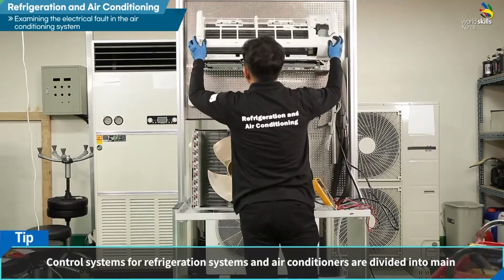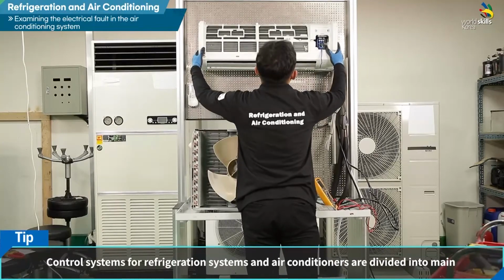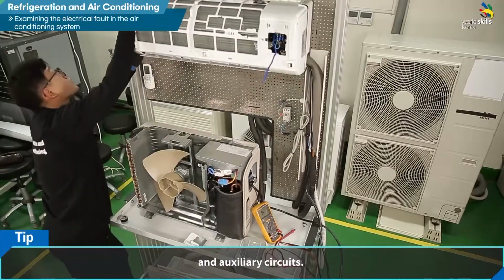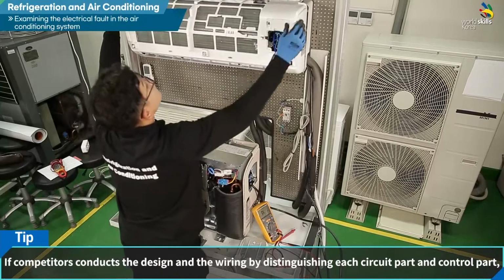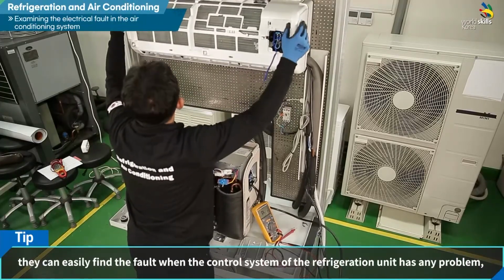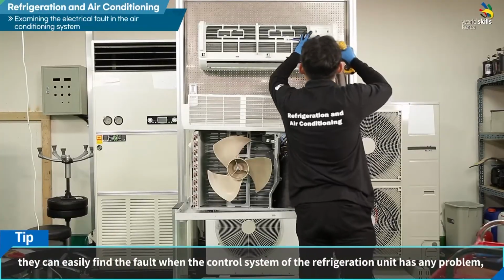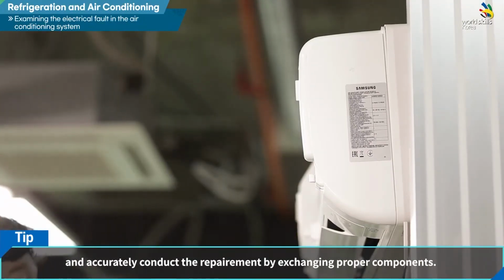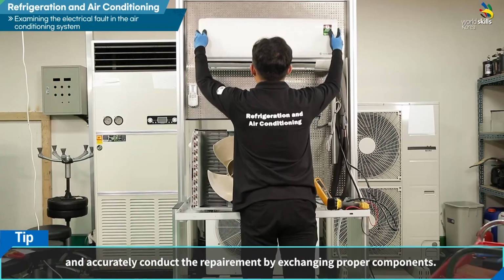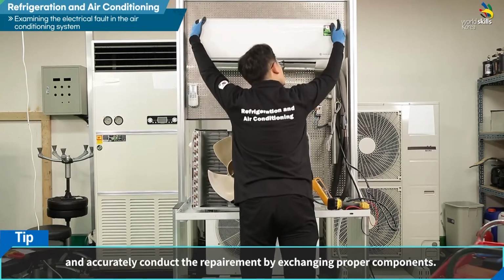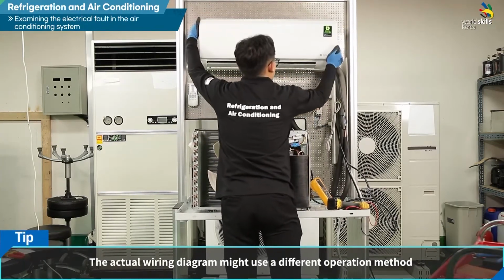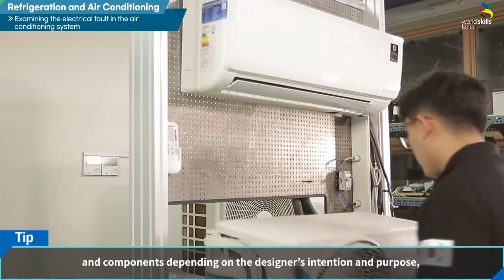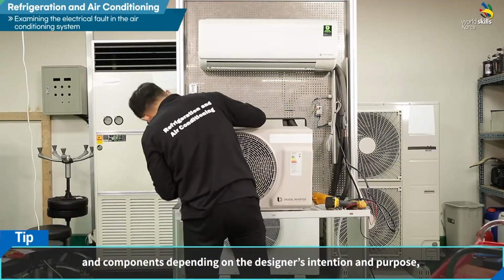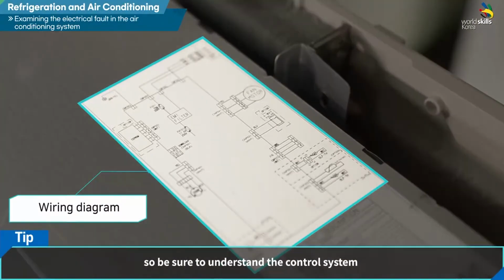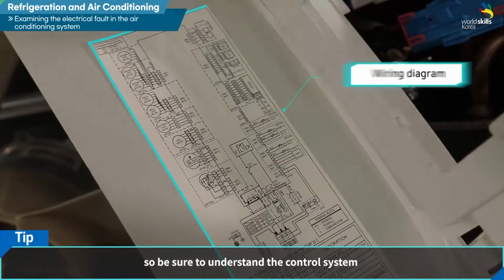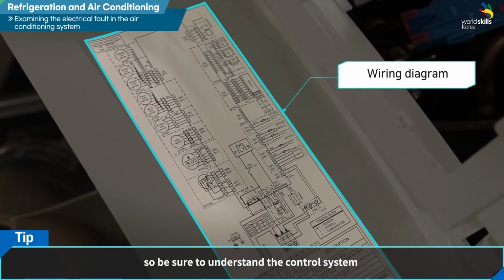Control systems for refrigeration systems and air conditioners are divided into main and auxiliary circuits. If you conduct the design and the wiring by distinguishing each circuit part and control part, they can easily find the fault when the control system of the refrigeration unit has any problem and accurately conduct the repair by exchanging proper components. The actual wiring diagram might use a different operation method and components depending on the designer's intention and purpose. So, be sure to understand the control system by checking the wiring diagram provided by the manufacturer.